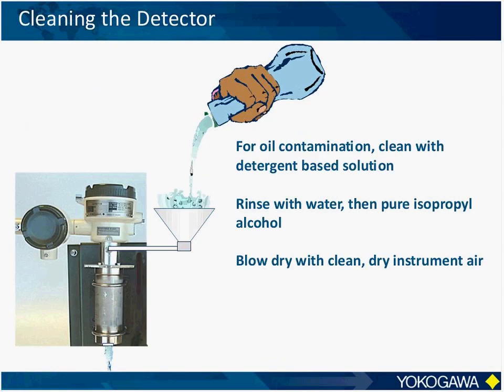Now, in a perfect world, the detector would only see a clean and dry sample, but we know in the real world this isn't the case. These samples can often be contaminated with seal oil, sometimes to the point where the detector is completely flooded with the oil itself. Now, vibrating element detectors can be salvaged from such an event on site. The detector can be easily cleaned with a detergent-based solution, rinsed with water, then rinsed with pure isopropyl alcohol, and then the detector can be dried with instrument air, calibrated, and then placed back in service. Typically, there's no need to send the unit back to the factory for repair.